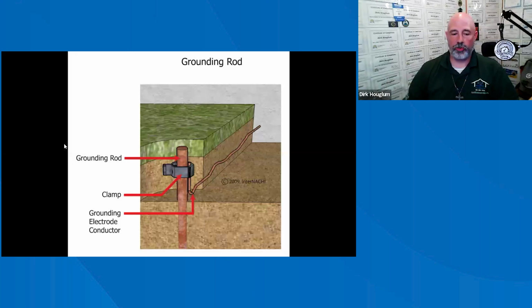This is what your typical grounding rod looks like. It goes 8 feet into the ground, and you have to have it 6 feet apart from another grounding rod in most jurisdictions, though some jurisdictions still only require one grounding rod. When I was in electrical school, they told us not to put the grounding wire pointed up like that—it should point down, just in case lightning hit it, so it wouldn't bounce up and hit the siding. But there's no actual rule saying it has to go up or down in that clamp.